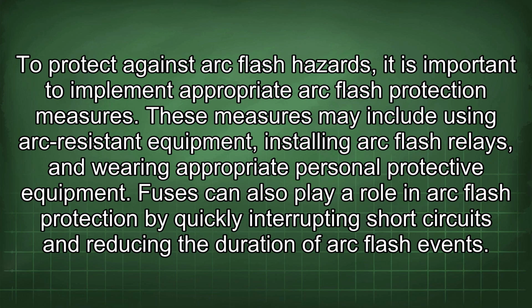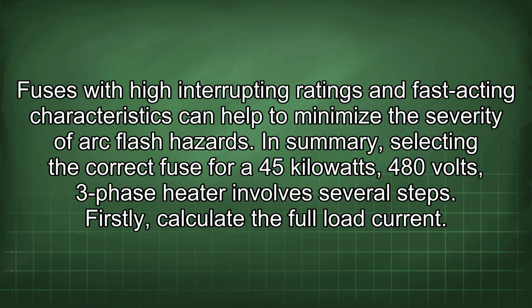Fuses can also play a role in arc flash protection by quickly interrupting short circuits and reducing the duration of arc flash events. Fuses with high interrupting ratings and fast-acting characteristics can help to minimize the severity of arc flash hazards.